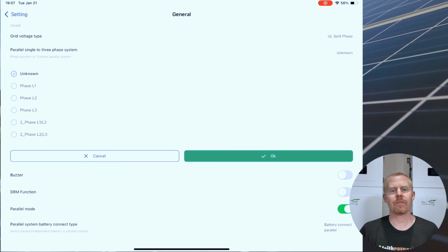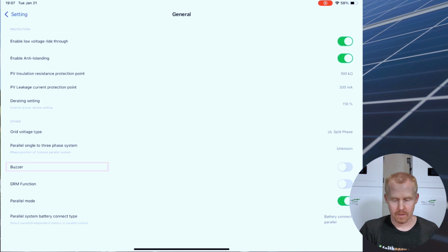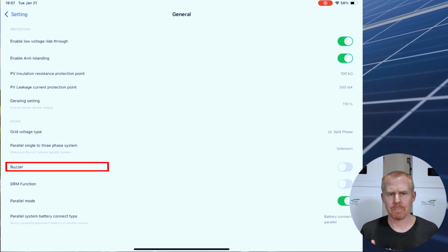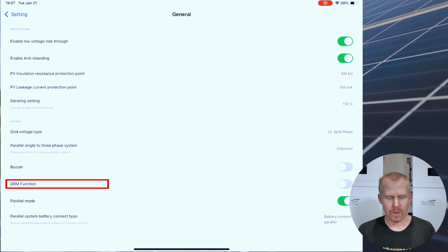The next option, if you are configuring a 3-phase system, you need to basically assign which inverter is going to be what leg in that 3-phase system. Is it going to be L1, L2, or L3? Buzzer. Do you want your system beeping when you press the button on the side of the inverter? I'm not quite sure what the DRM function is for. It's another one of those options that I believe is for grid interconnectivity.